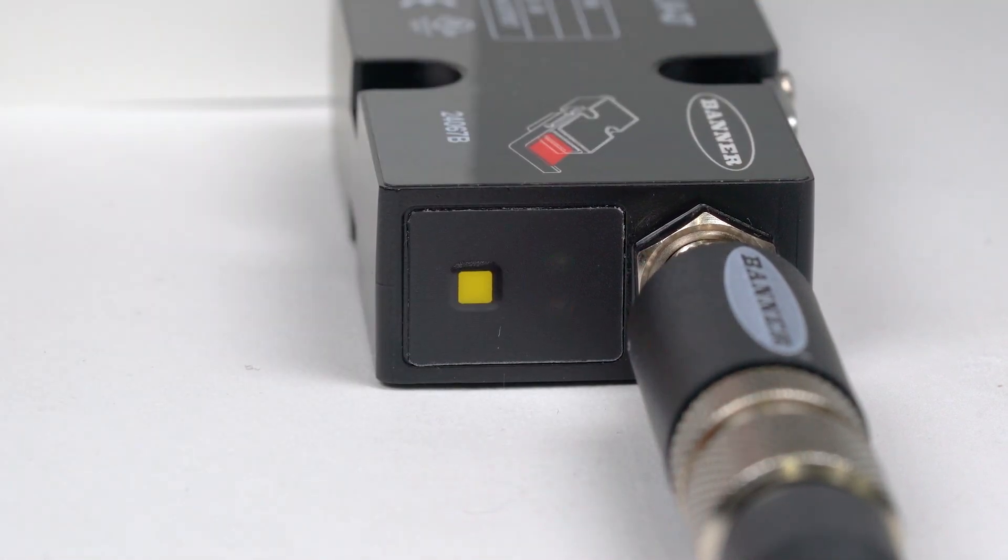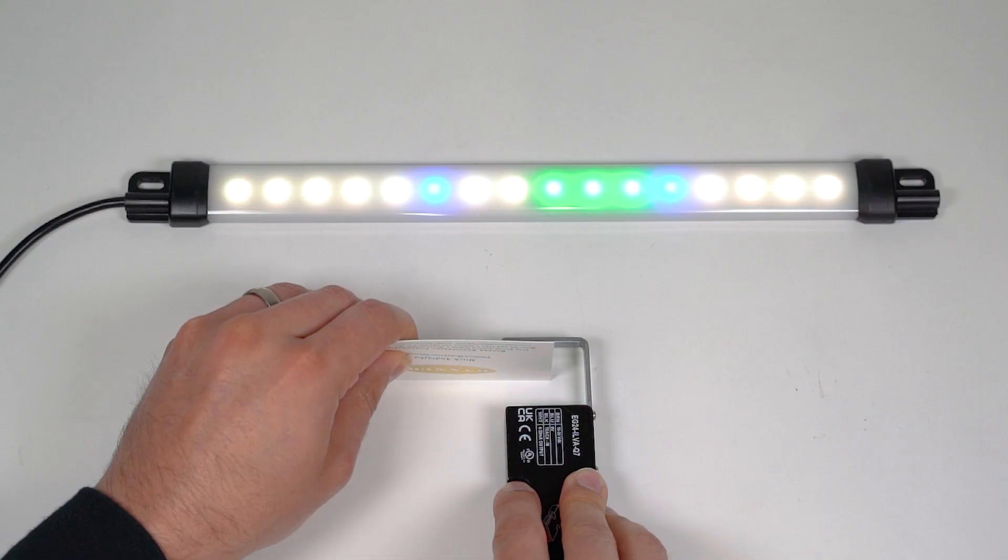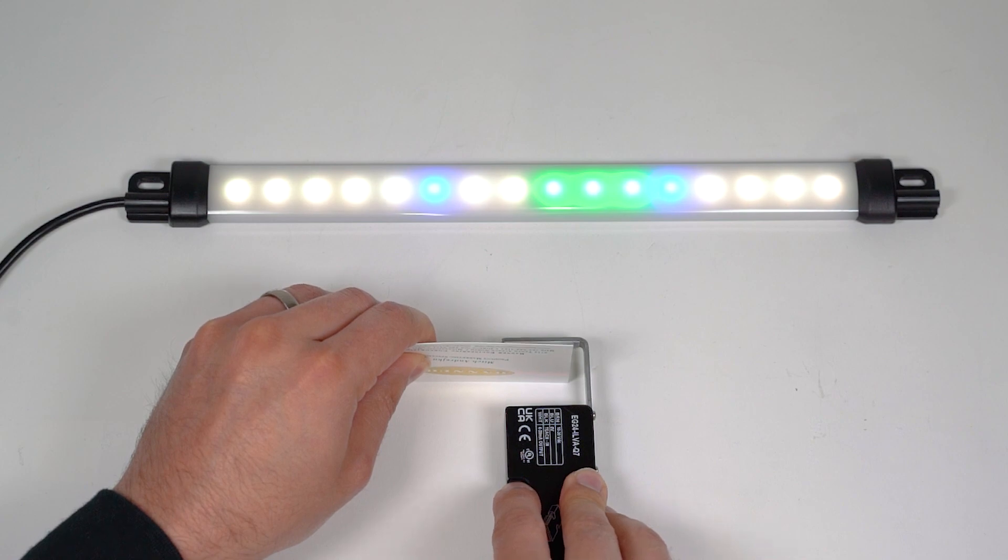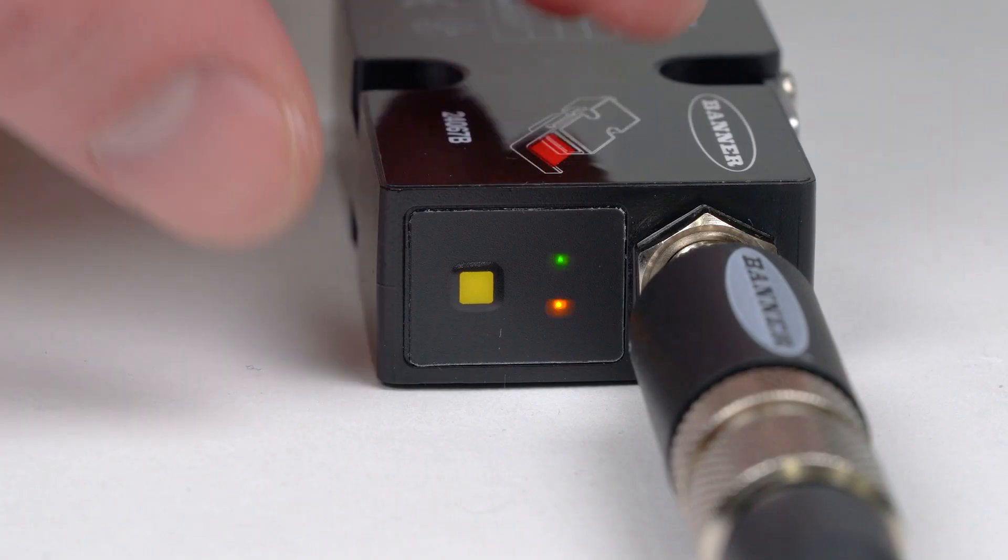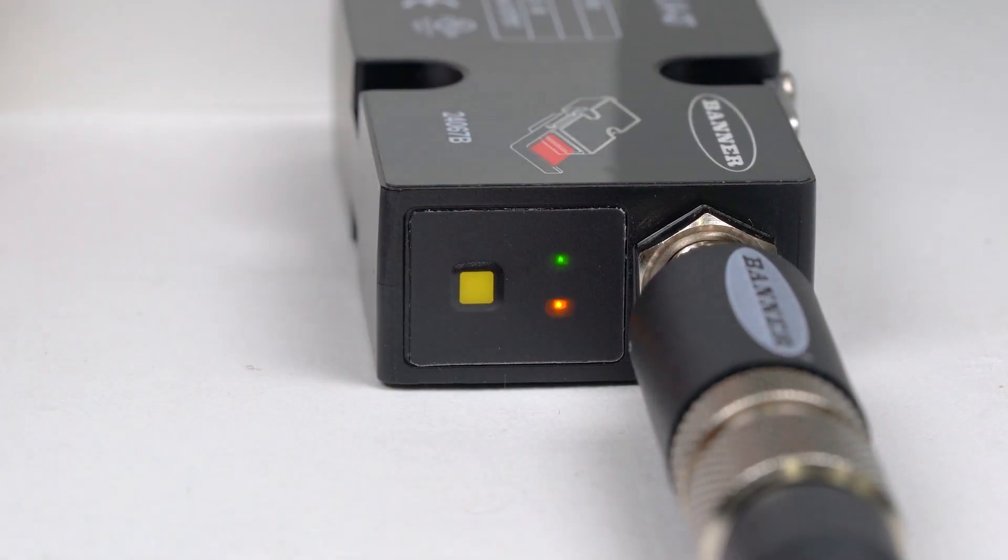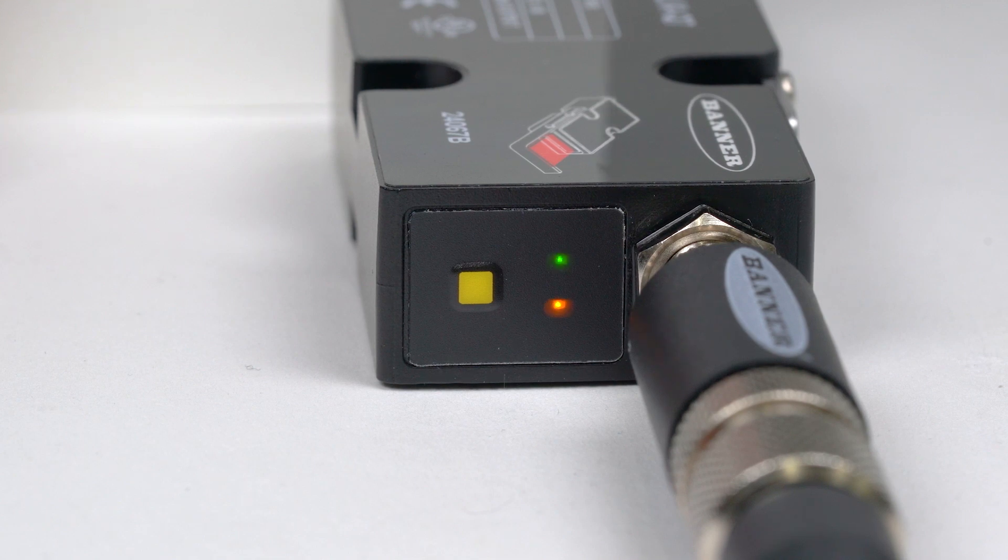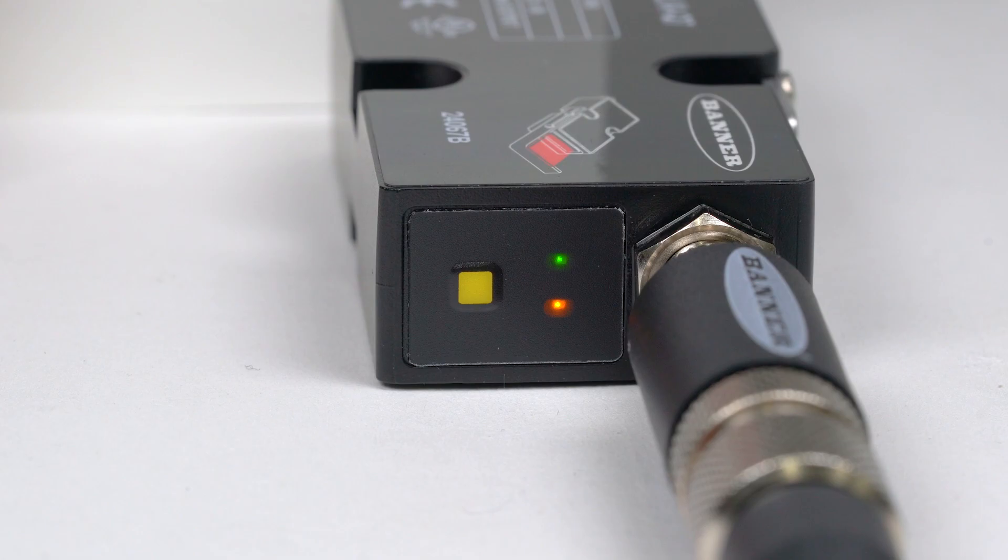When the LEDs begin double flashing, move the target to a position that will represent a 20 milliamp output and push the button one more time. The green LED will flash twice to confirm that the new field of view has been set and the sensor will return to run mode.